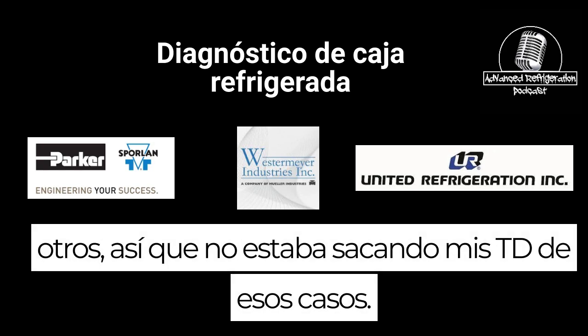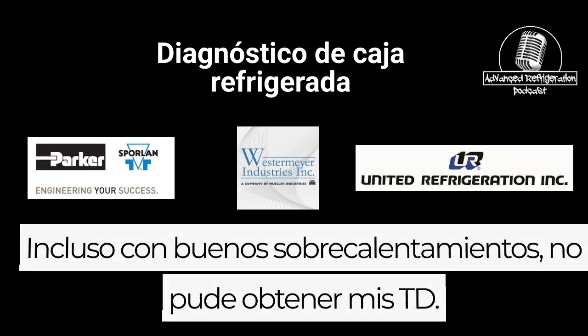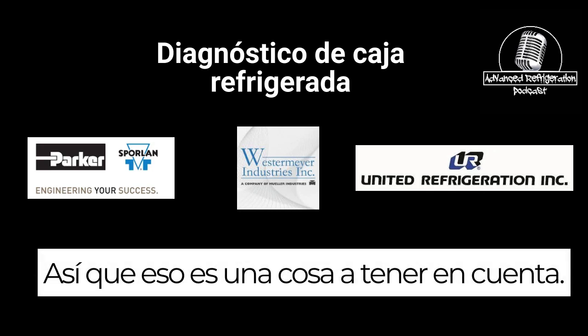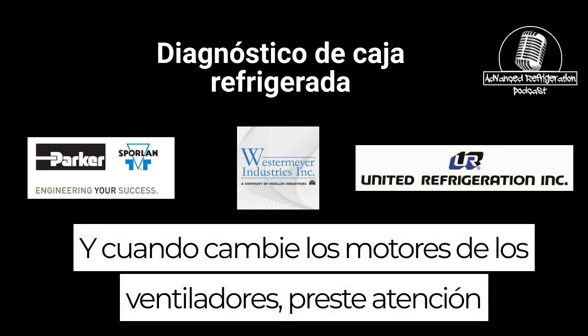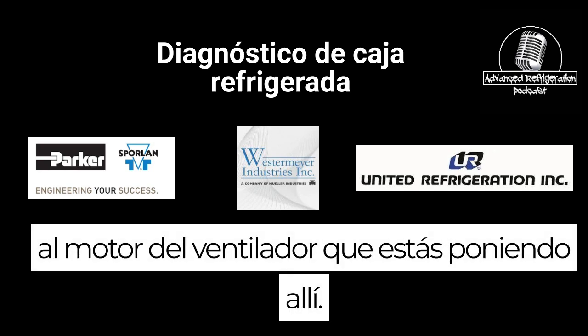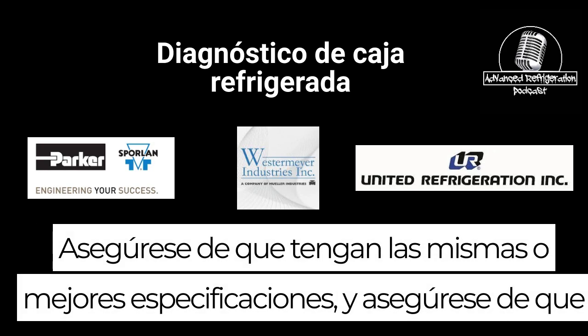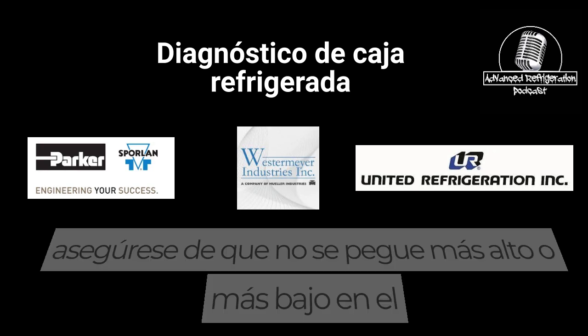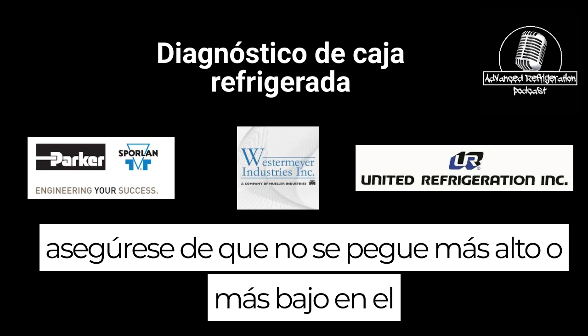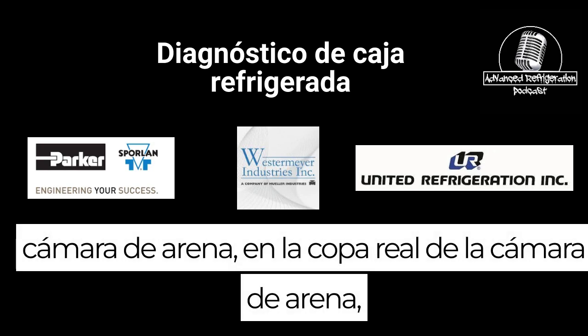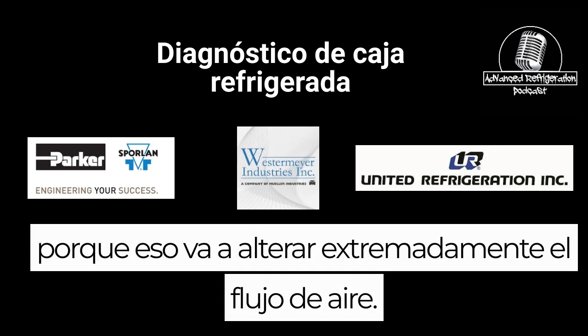So I wasn't getting my TDs off those cases. Even with good superheats, I couldn't get my TDs. So that's one thing to keep in mind. And when you're changing fan motors, please pay attention to the fan motor you're putting in there. Make sure it's the same or better specs, and make sure that it's not sticking higher or lower in the fan plenum, in the actual cup of the fan plenum, because that's going to extremely throw off your airflow.